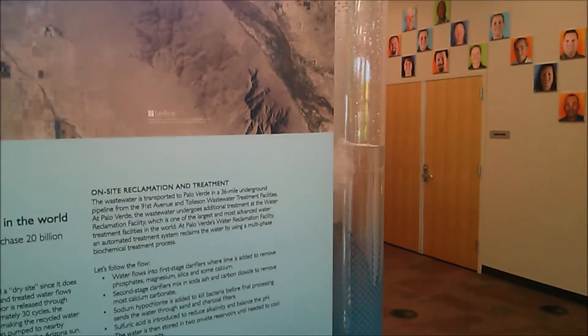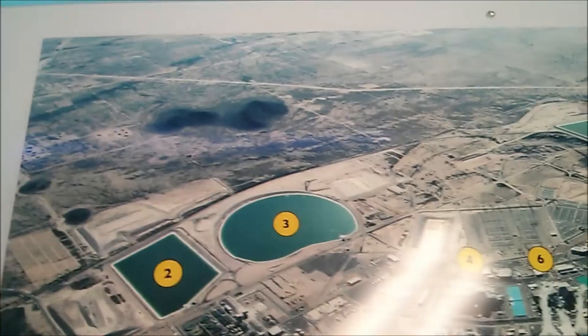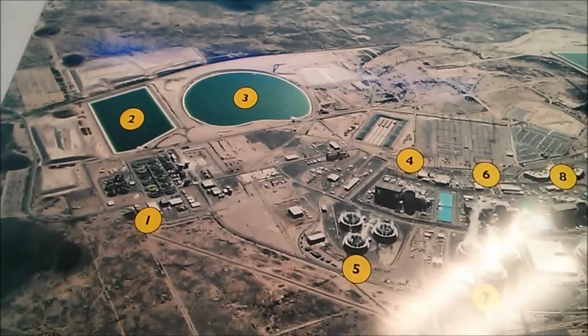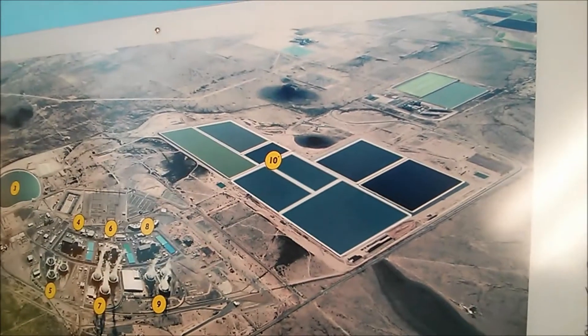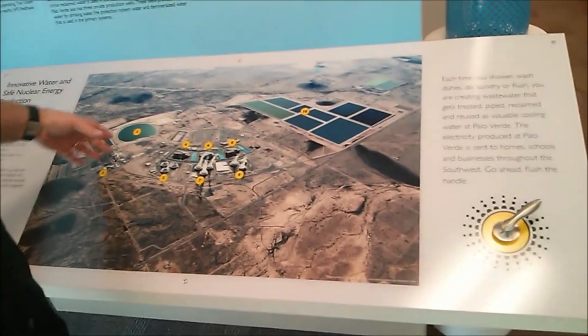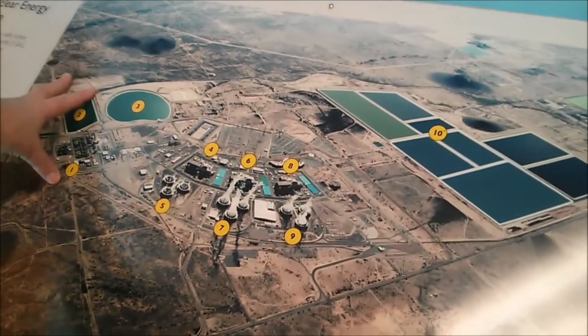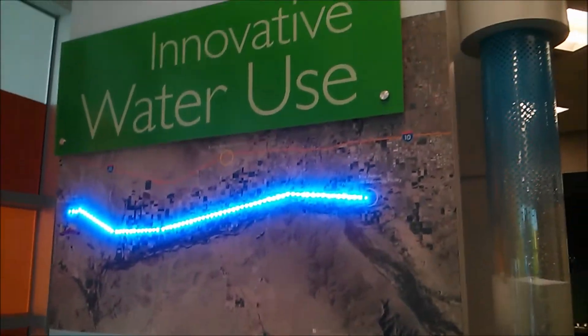The water is then treated at our own water reclamation facility, labeled number one, which is the water source for our cooling systems. The cooling towers are at five, seven, and nine for units one, two, and three. The water we get has radioactive material in it — either natural or man-made — that comes in through the waste system. It is not becoming radioactive by going through the nuclear plant; it was already radioactive when we got it. So as people in the valley communities flush their toilets, take showers, and wash dishes, they are providing the cooling water for Palo Verde.